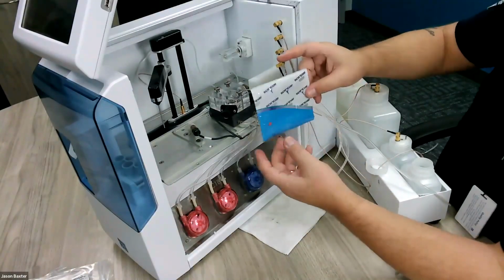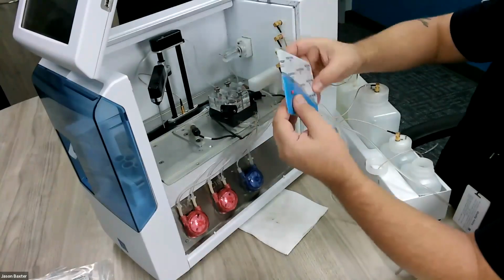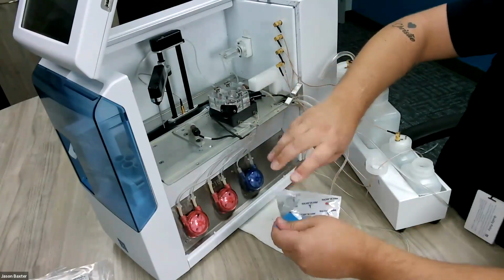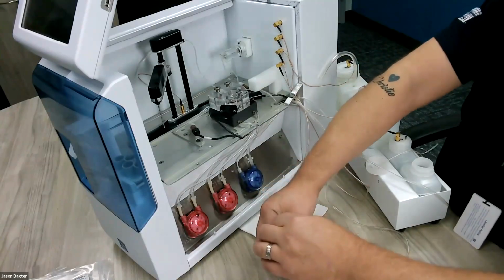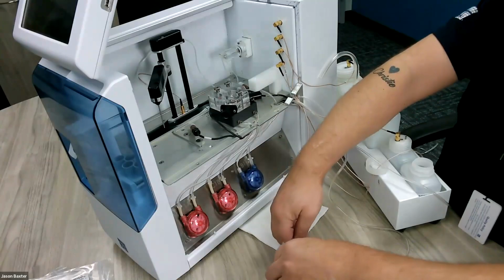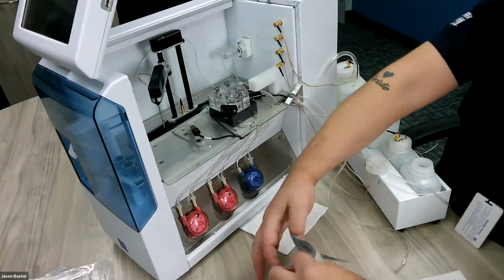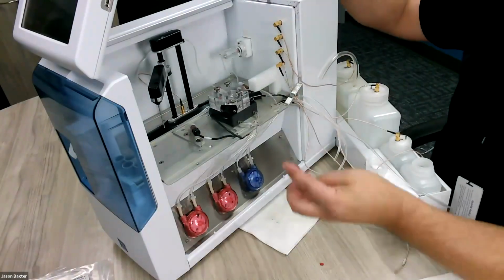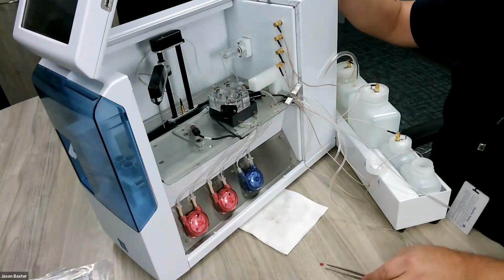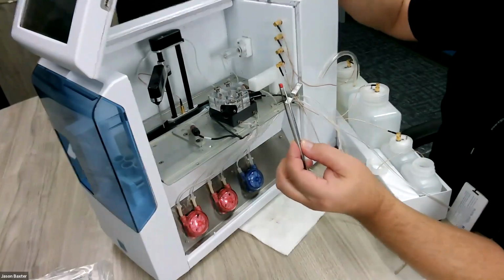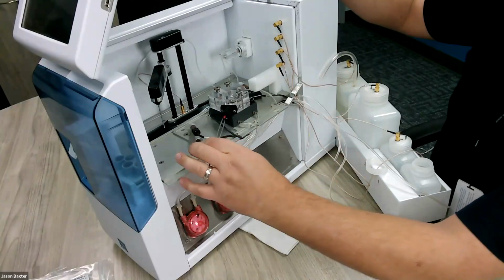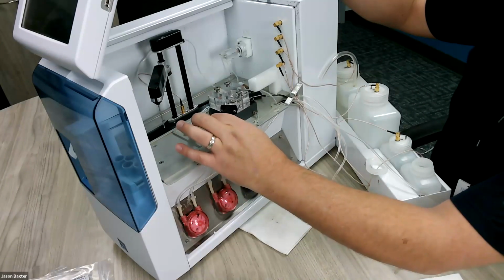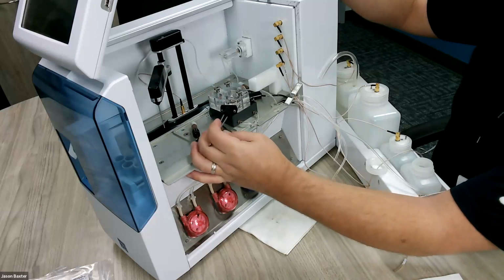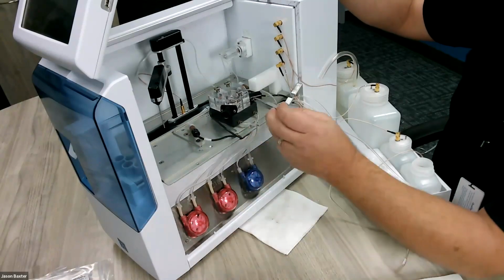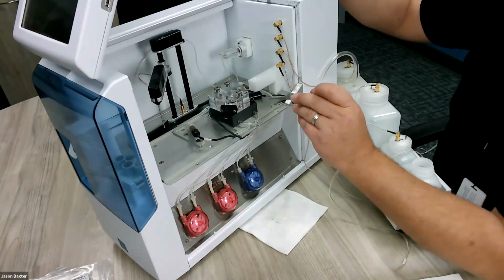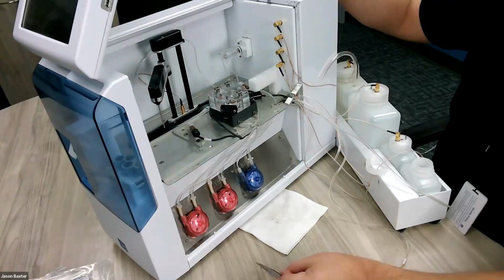Last part for your sample chamber, take your stir bar, tear open the stir bar packet. Now, I've seen a few different ways that people try to install the stir bar. I'm going to show you the way that I found to be the best. Your results may vary. If you have a different way that you like to do that's better than this, by all means, proceed. This is where your tweezers come into play. So what I like to do is I'll pick up the magnetic stir bar, hold it by the tweezers, and then I will simply go in through the sample chamber through probe A, line it up in the middle of that sample chamber, and simply let it go. The magnetic attraction between the top of the stir motor and the magnetic stir bar will just let it drop out and it'll nest right into place.